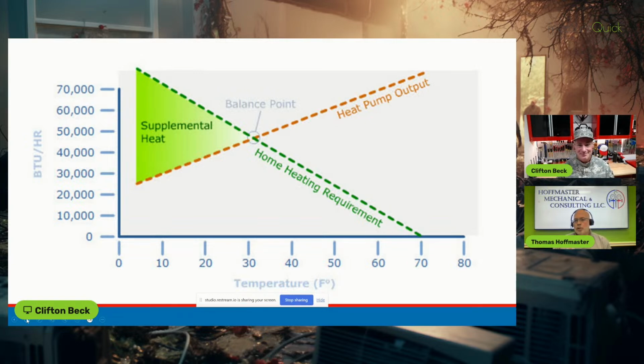Exactly. That sunny day at 30 degrees is a little different than that overcast rainy day at 30 degrees. So once we run the numbers and the math works, we start setting a range: we'll lock out the furnace above this temperature, lock out the heat pump below this temperature, but in that gap, with the right controls and thermostat enabling this, we'll let the heat pump come on first.